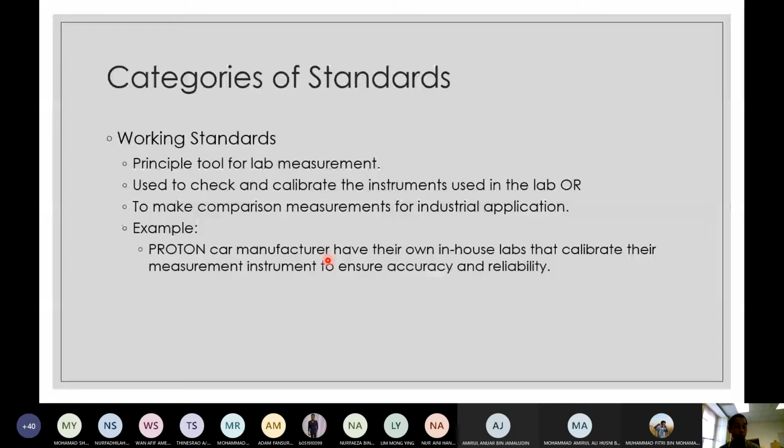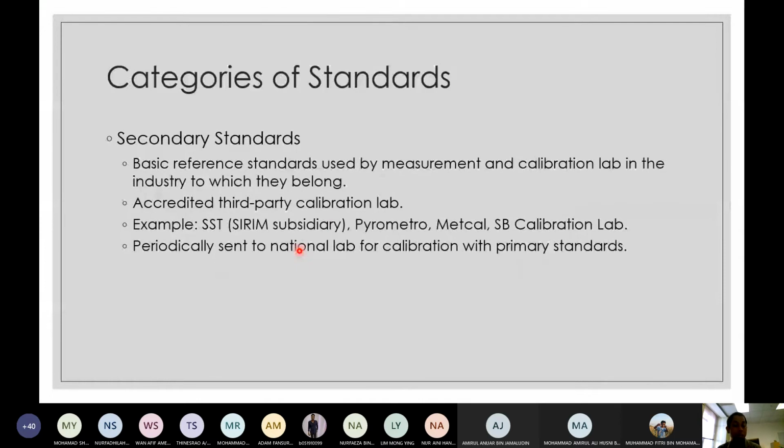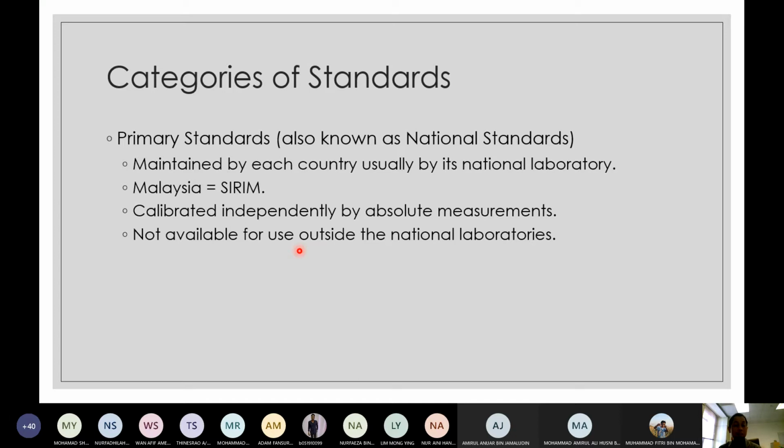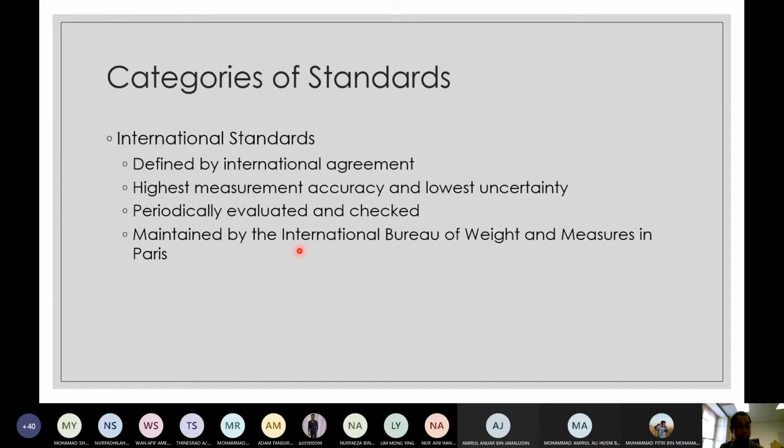So let's see the sequence now. At the bottom of the triangle, we have the working standard. Let's say you are an engineer in Proton. First, you have your own measuring instrument that you use for everyday work. Then you must ensure that your measurement is accurate and reliable. So from time to time, your equipment needs to be sent to the secondary standard, a third-party calibration lab, so that it can be calibrated and make sure it performs correctly. The lab themselves have their own calibration equipment, which they need to send from time to time to the SIRIM National Standards Lab. And then SIRIM must ensure that their measurement and calibration equipment comply with the international standards.